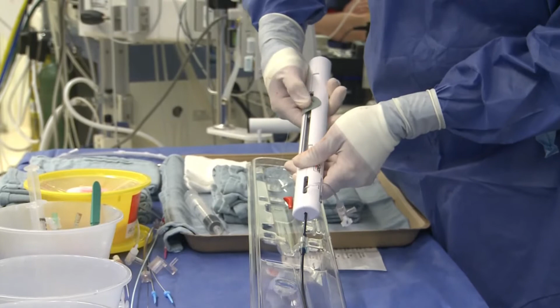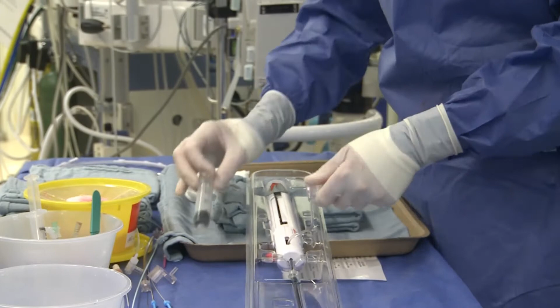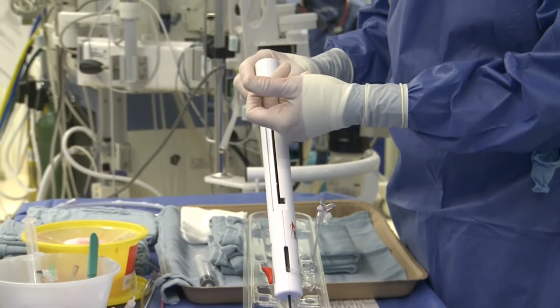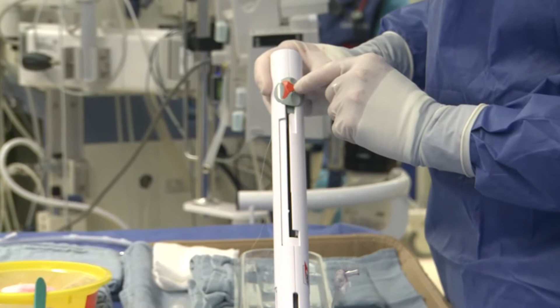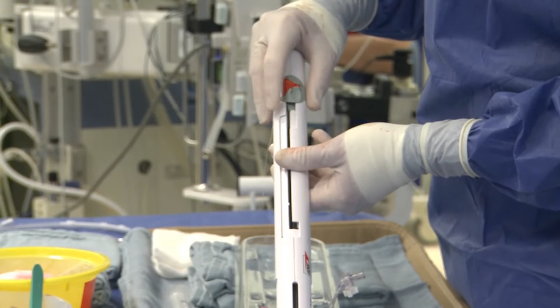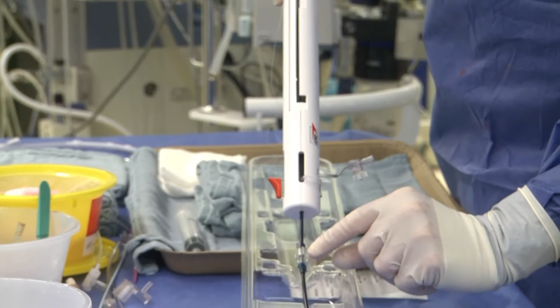So once I have it loaded in, we'll just flush the device, we'll flush the delivery system one more time. So we're good to go. Now, just like the Helex family, there is a retrieval cord attached to the right atrial disc. So if we decide to take the device out, you don't remove this red cap, or this little red tab right here. You keep that on. That keeps the retrieval cord locked in the handle, and then you would separate the delivery system right here.